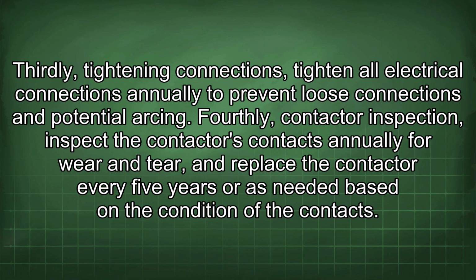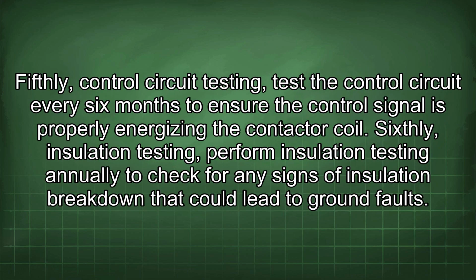Fourthly, contactor inspection. Inspect the contactor's contacts annually for wear and tear, and replace the contactor every 5 years or as needed based on the condition of the contact. Fifthly, control circuit testing. Test the control circuit every 6 months to ensure the control signal is properly energizing the contactor coil. Sixthly, insulation testing.